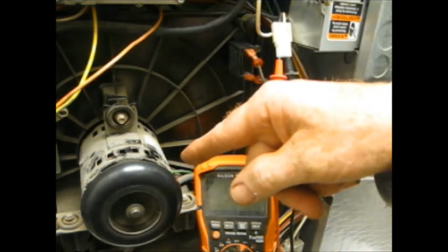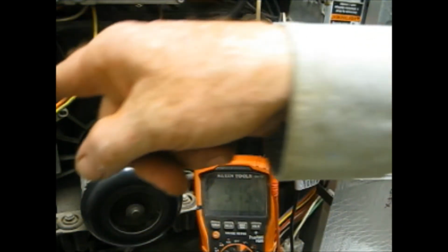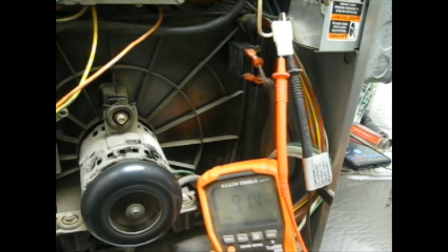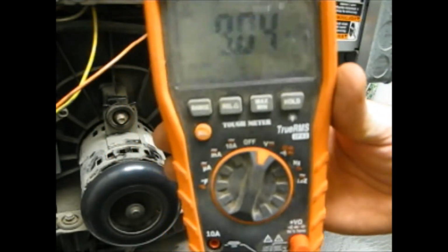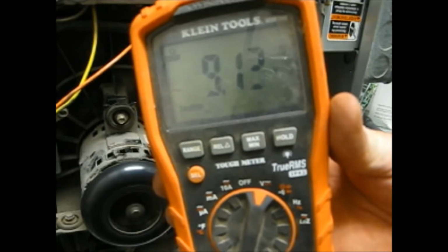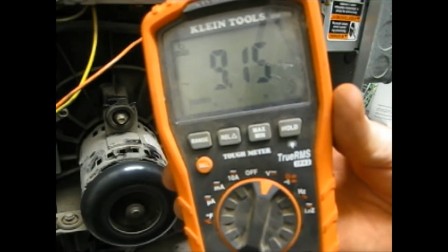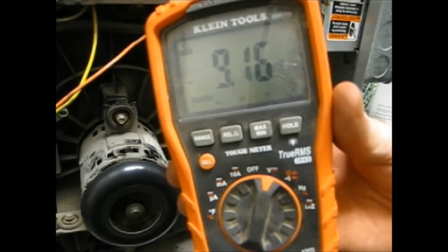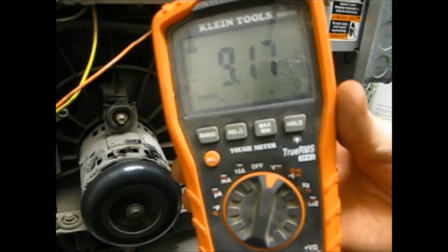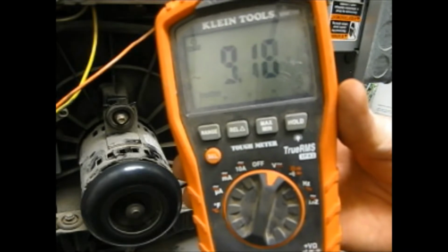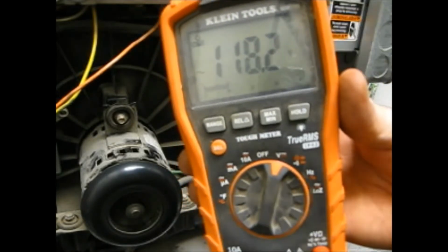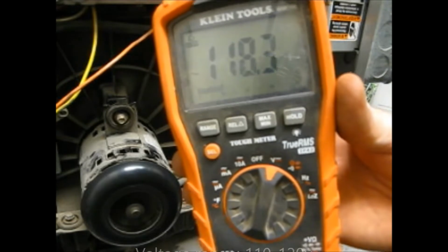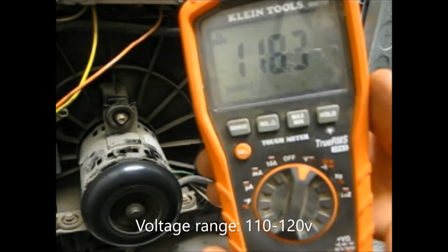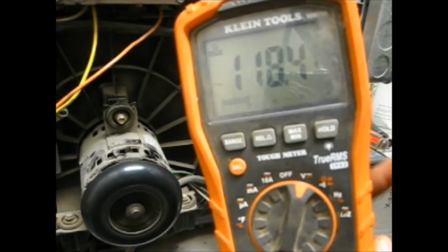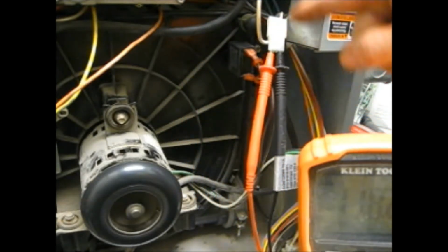Okay, we hit 90 seconds. So we have the inducer motor running. Waiting for 120 volts. I just heard the click. Okay, we have 118 volts. Well, that's just fine.